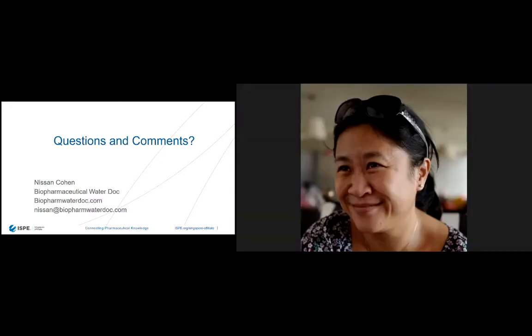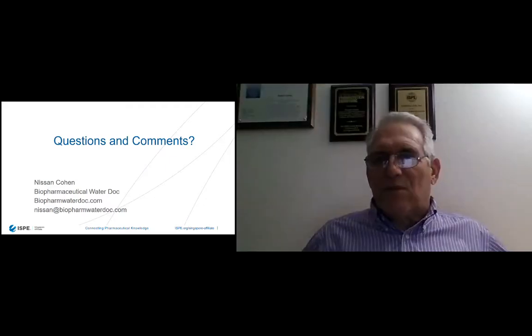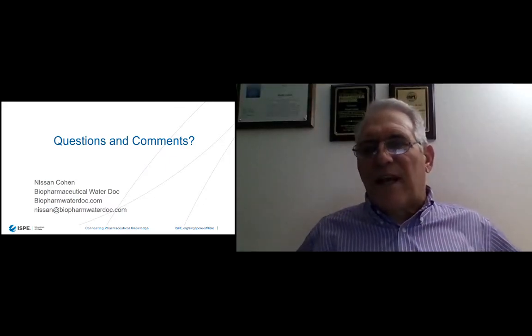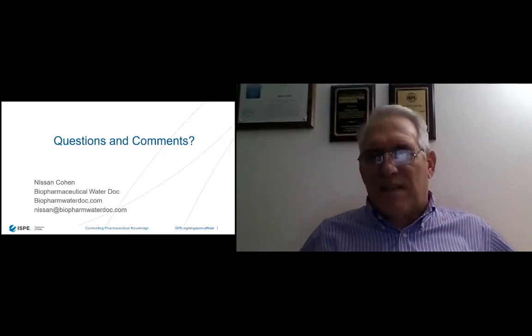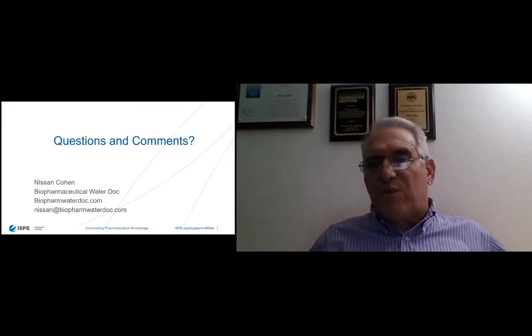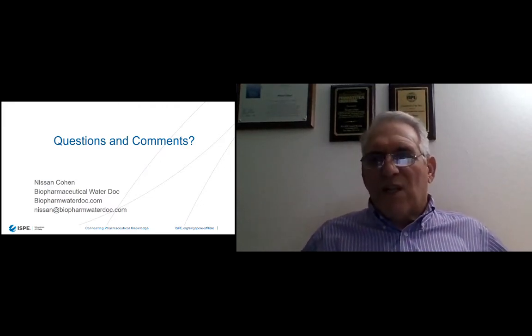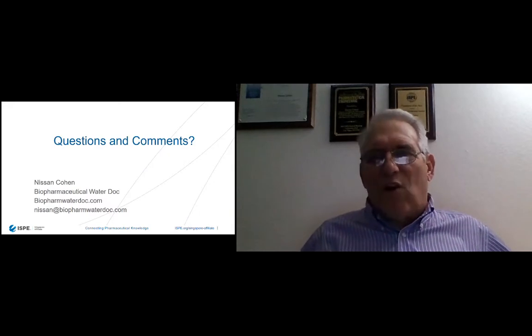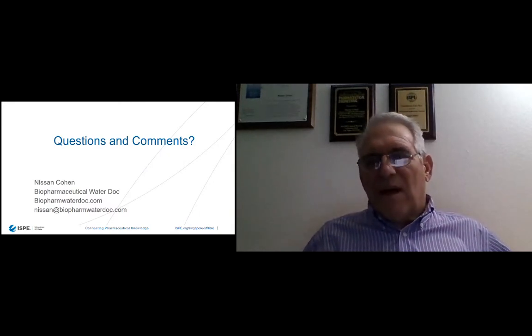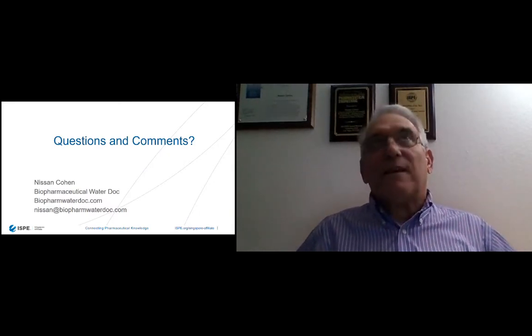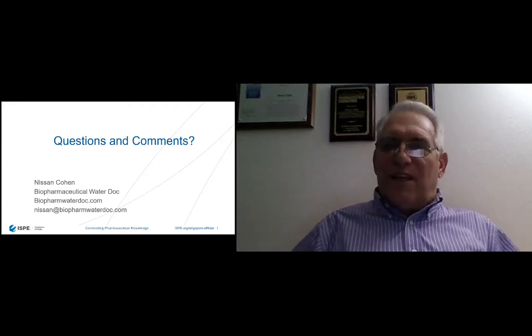Thank you. Now, Watson TVP asks, can low ferrite content of piping, instrument, and valves help reduce rouge rate or not? Yes, absolutely. So let's say if we were using titanium as an example, we would have no rouge whatsoever, a very minimal amount of rouge. The point is that the alloys are dependent upon what the designer actually did initially.